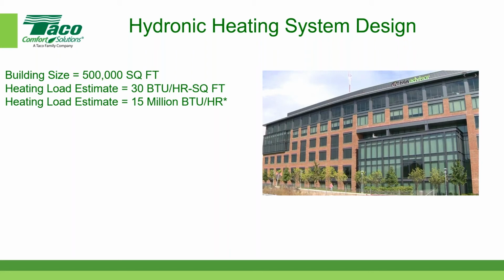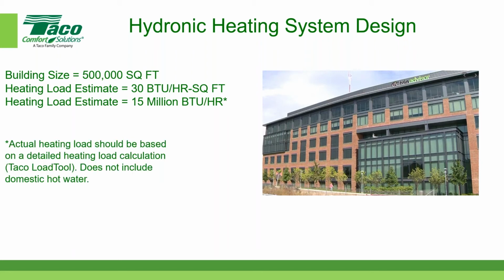I have an asterisk here because I always like to make the note that actual heating load should be based on a detailed heating load calculation. You can use the TACO load tool, which we have at the end. I'll show you how to download that for free. And our system does not include domestic hot water, so we're just allocating 30 BTUs per hour per square foot for space heating. We're not doing any domestic hot water heating. So that's just a quick estimate of the capacity our system needs to be for this imaginary building.